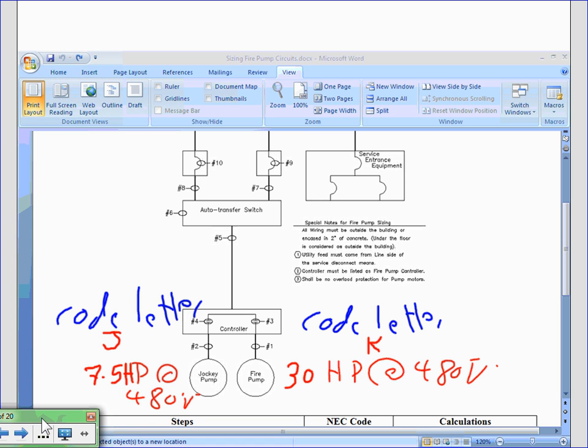All you need for this system is really, first, the jockey pump. I have a 7.5 horsepower jockey pump and a 30 horsepower fire pump, and both of them are running at 480, and I need a code letter J and K. A code letter J and K. And I want you, gentlemen, to size all these 10 things for this system.